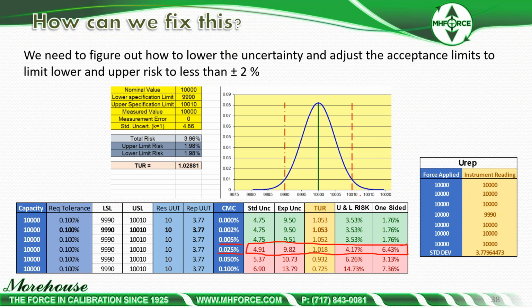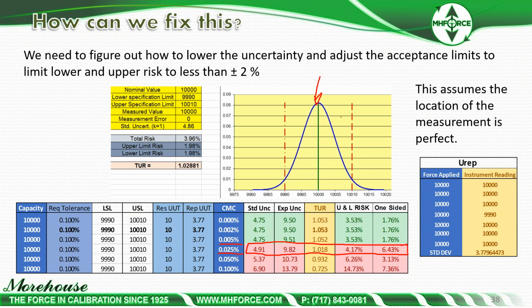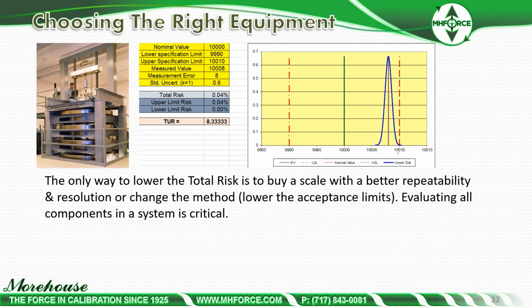This also assumes the location of the measurement is perfect. So it assumes 10,000 pounds is 10,000 pounds. If we're over here at the resolution such that this thing's only going to read 10,000 or 9,990 or 10,010. So, again, the only way to lower the total risk is to buy a scale with better repeatability and resolution, or change the method, lower the acceptance limits. Evaluating all components in a system is critical.